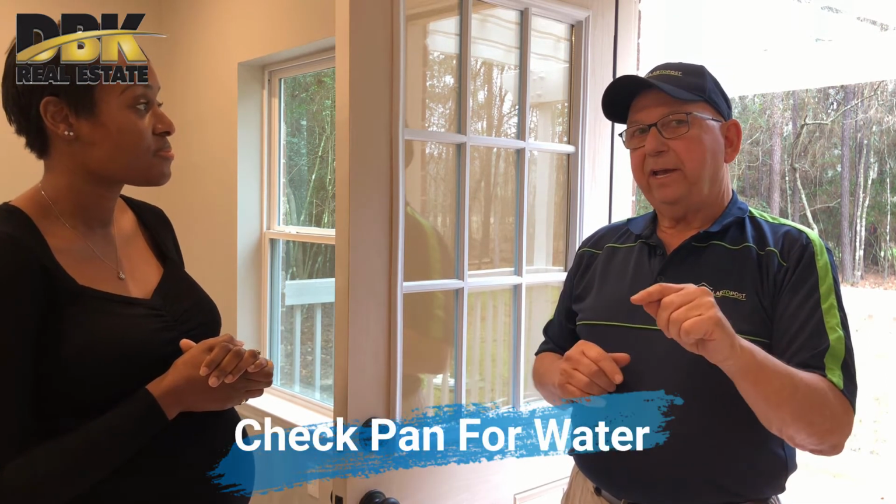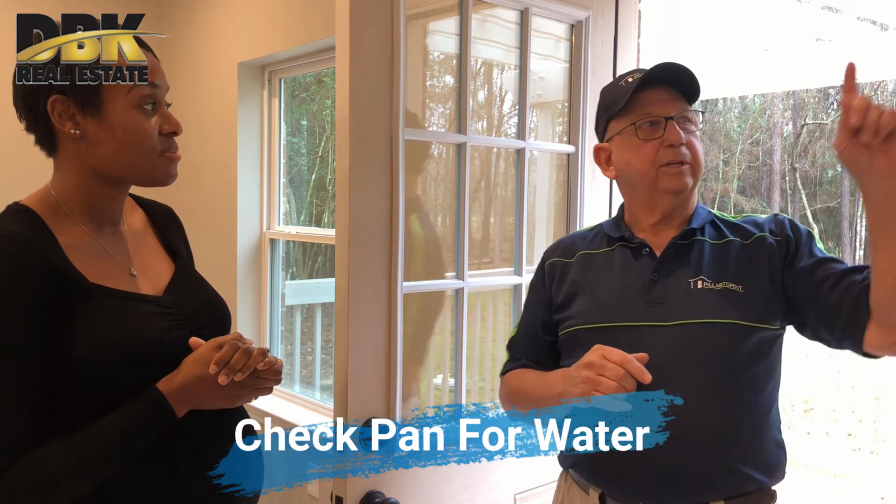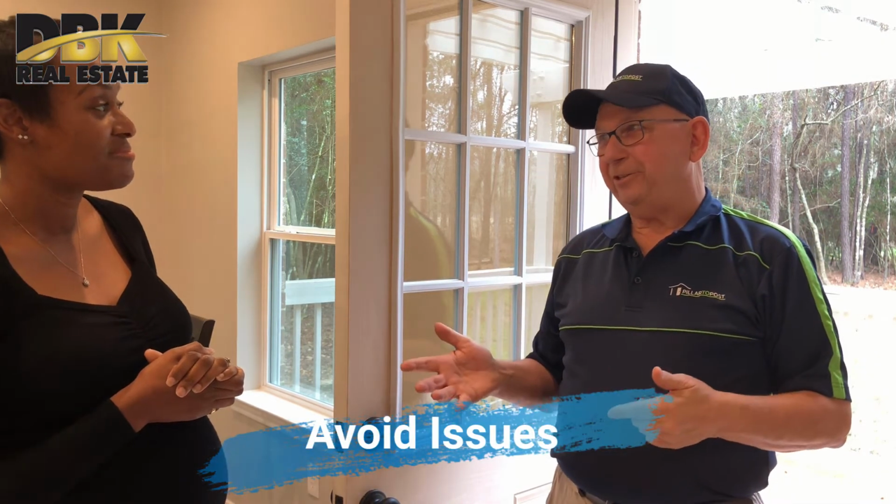That pan also drains outside, just below the roof. It's called a soffit, and there'll be a little pipe sticking out. If that's dripping, you've got water in that pan. You don't want any water in the pan. It can clog up, and that's why if they come twice a year, you won't have that issue.